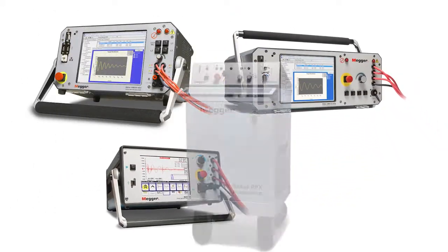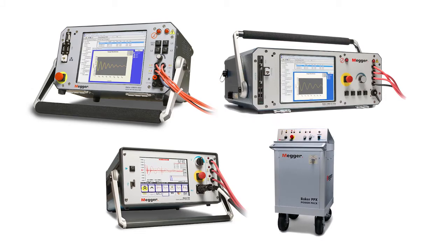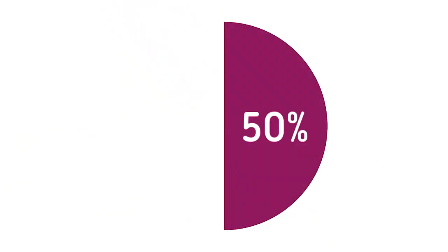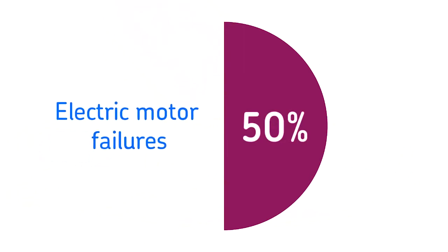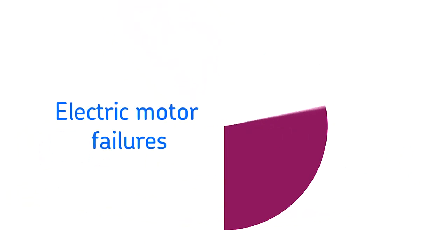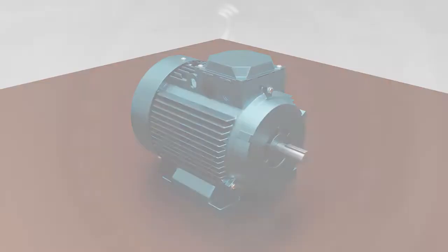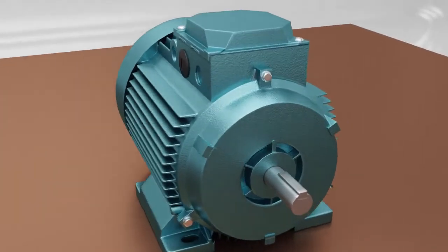Megger-Baker Instruments static motor analyzers test the insulation system of an electric motor. The motor insulation system is responsible for up to 50% of electric motor failures, even more on higher voltage motors. Let's take a quick look at the motor insulation system.